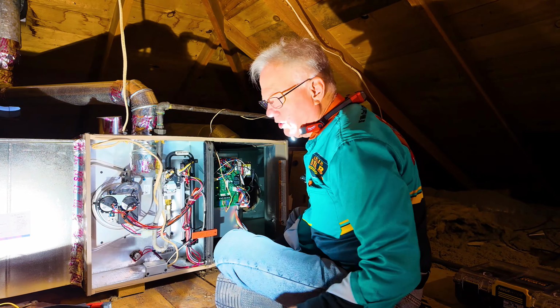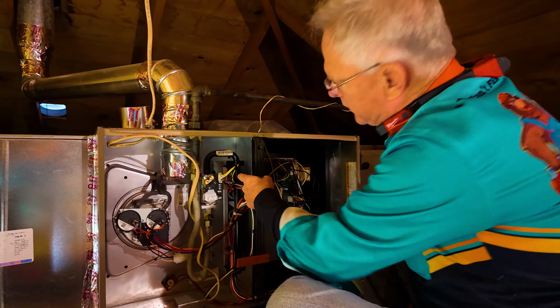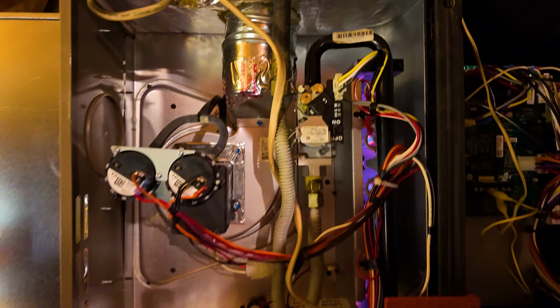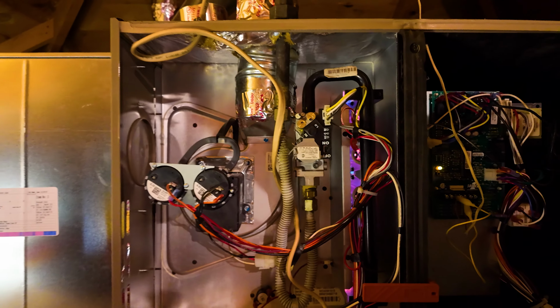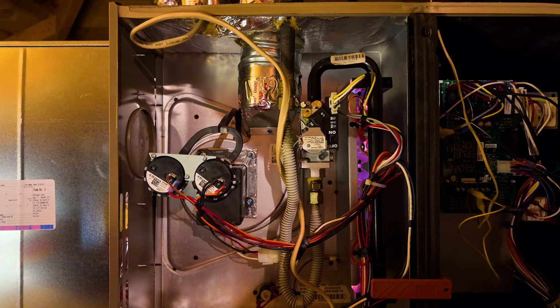Okay, so I'm calling for heat again now. I'm going to turn off my lights because I want you to see in here when the igniter comes on. Okay, you can see it back in there now, probably glowing orange. It's hard to do with this video, but now it's glowing orange in there. Now it's going to open the gas valve, and there's your blue flames flamed up, and the heat sensor is out. The flame sensing rod is obviously operating properly, or it would have already cut off the flame.